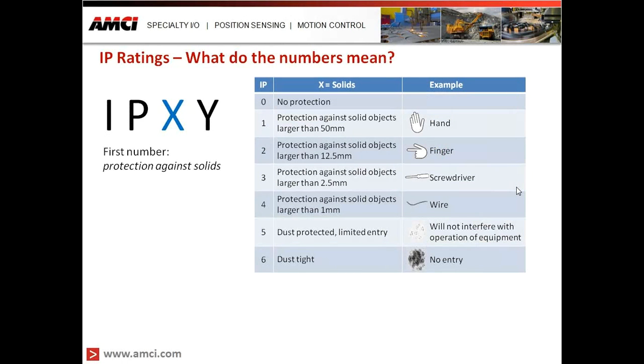Looking at the solid protection chart, the first number defines the protection against solids. The numbers start from zero and increase up to six, with each increasing number giving us protection from smaller and smaller objects, starting with no protection. If we select the number two, we're protecting against solid objects larger than 12.5 millimeters — roughly half an inch — which, as a practical example, would be a finger. Someone can't stick their finger inside that enclosure, damage the product, or get electrocuted.